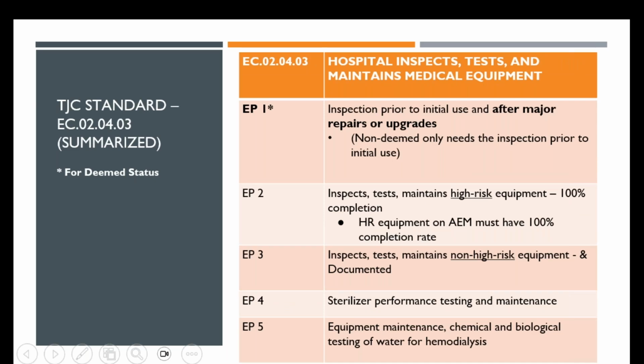There's going to be 5 slides for this one. It's a bit longer of a standard when it comes to the elements of performance. So under the standard, you need to perform an inspection prior to initial use. This includes your incoming inspections. If you are a deemed hospital, this needs to be documented, and inspections must be performed after any major repairs or upgrades. Just to note, at the VA, we're non-deemed, but in practice, we follow all the deemed rules. So we apply the same stuff. So it's kind of up to your discretion.